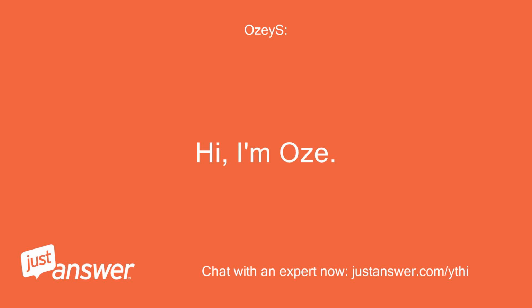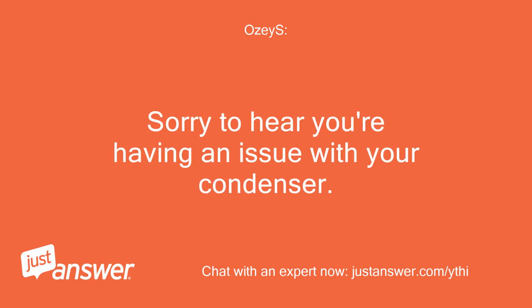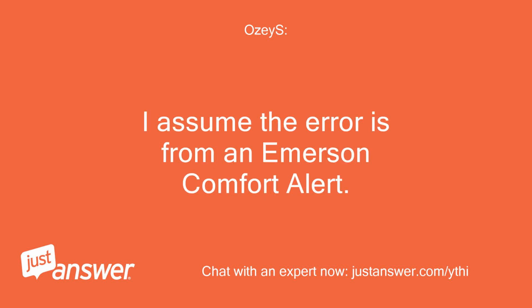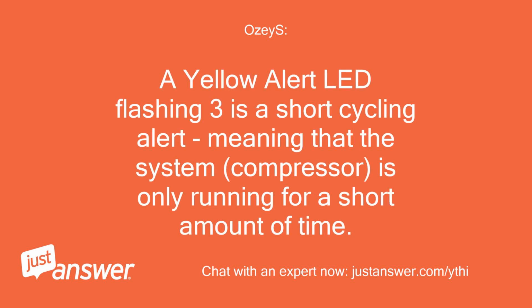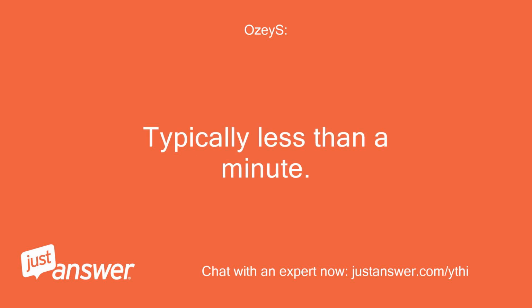Hi, I'm Oz. Sorry to hear you're having an issue with your condenser. I assume the error is from an Emerson Comfort Alert. A yellow alert LED flashing 3 is a short cycling alert, meaning that the compressor is only running for a short amount of time, typically less than a minute.